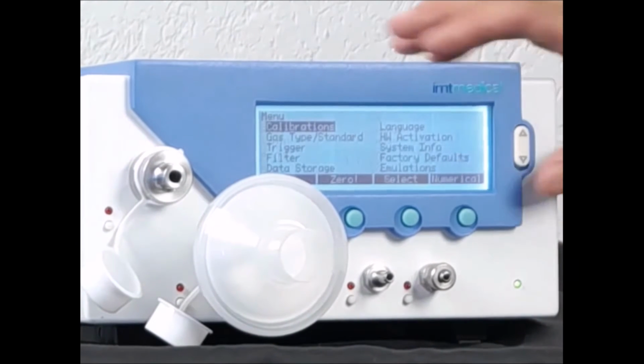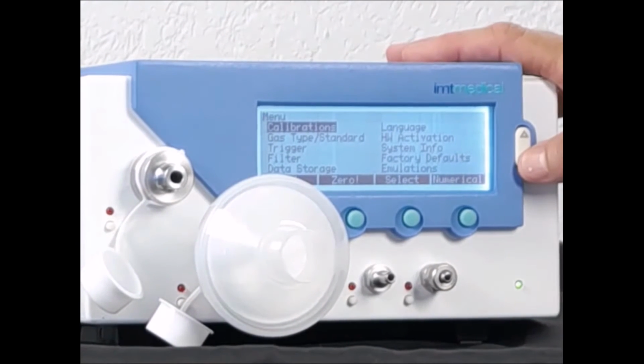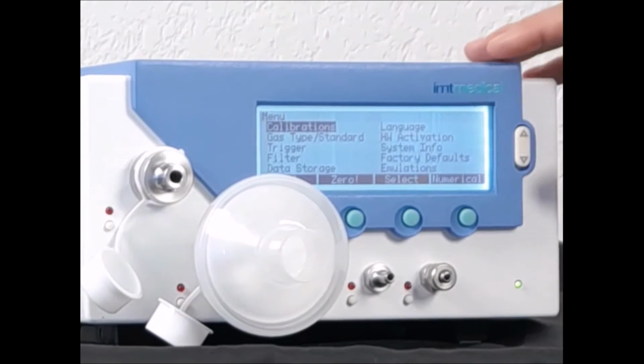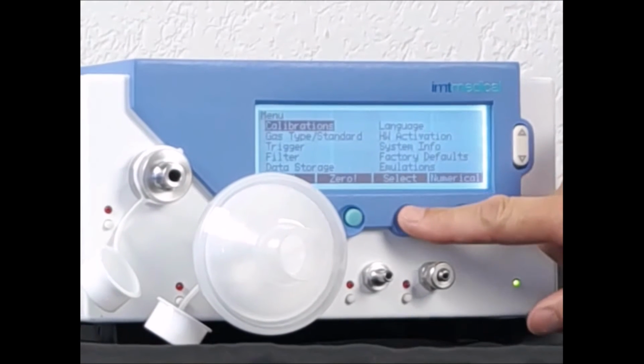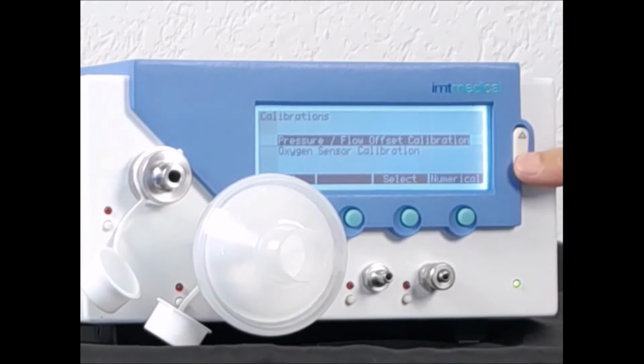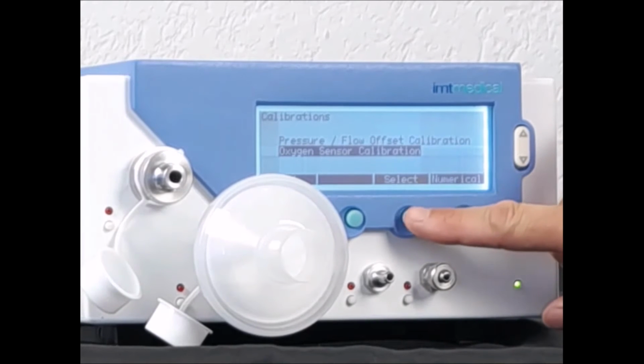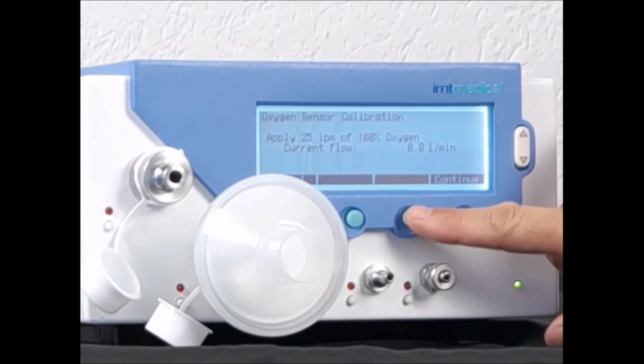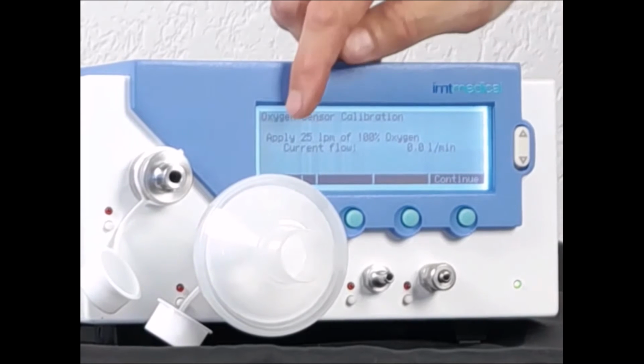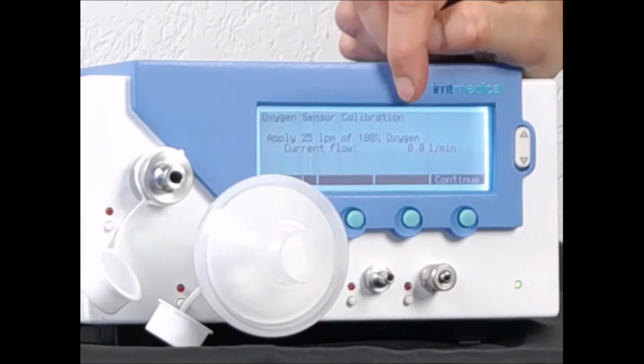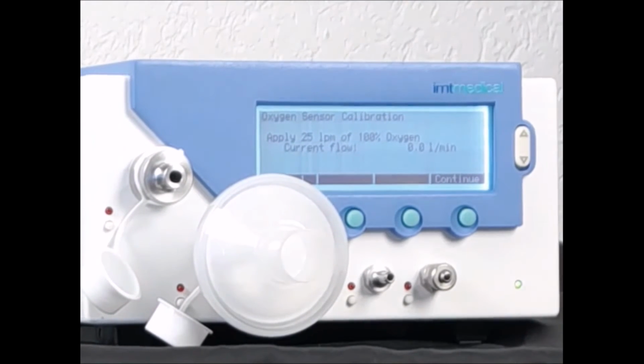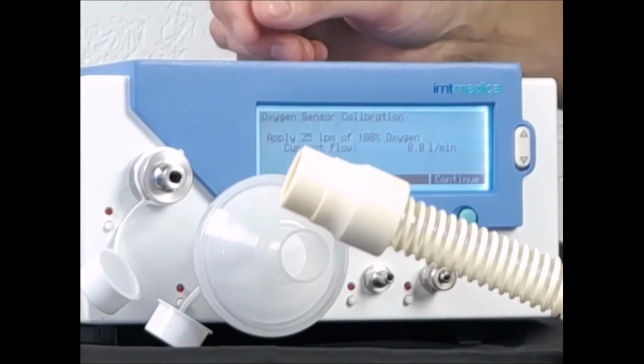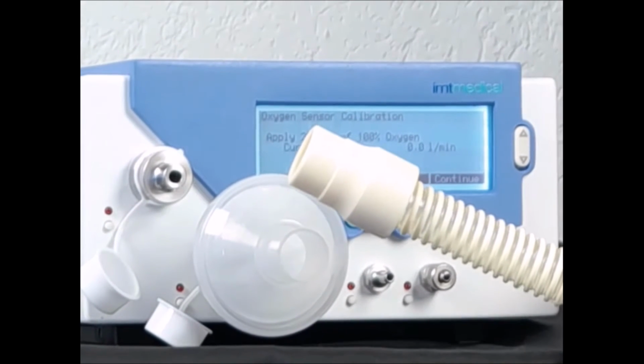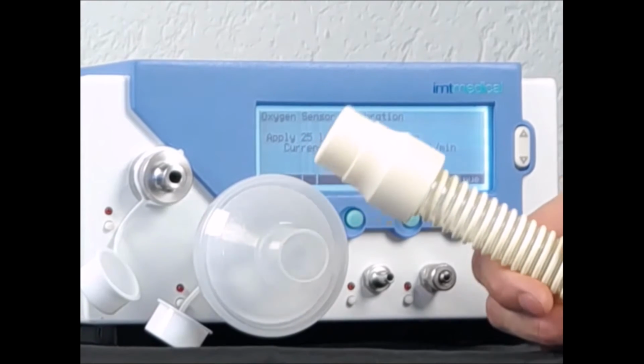I go to the menu. Where are the calibrations? I choose calibrations, select. I choose oxygen sensor calibration, select. And now it tells me to apply 25 liters per minute of pure oxygen. So what I'm doing right now is I'm using the service level of my ventilator to apply 100% oxygen, 25 liters per minute.